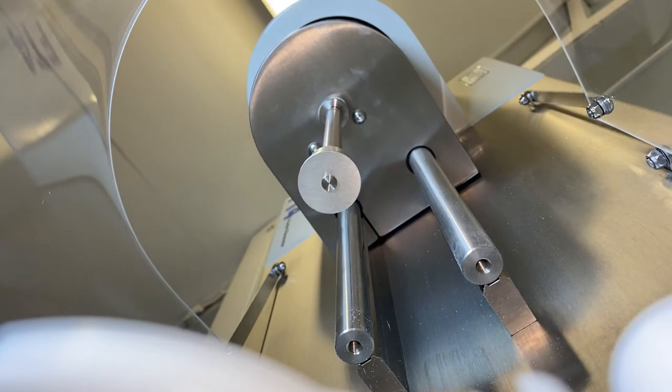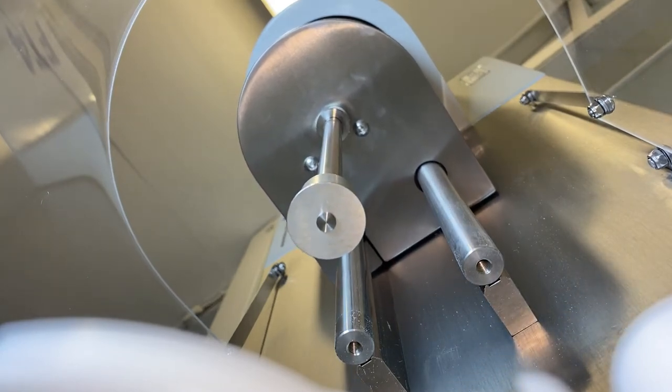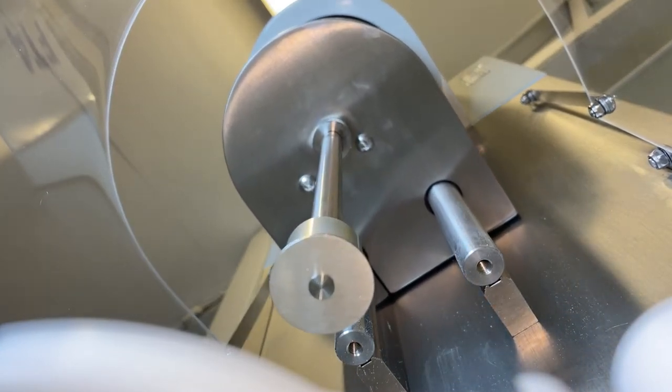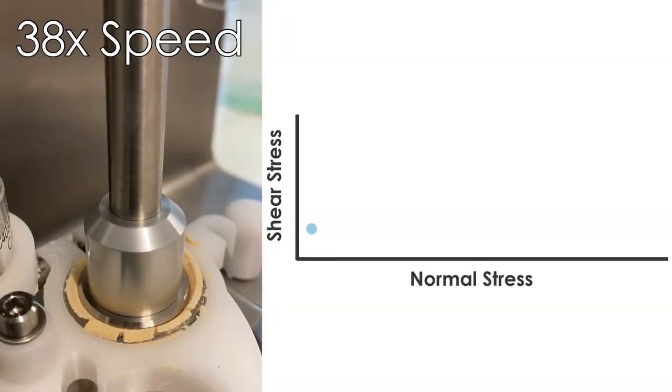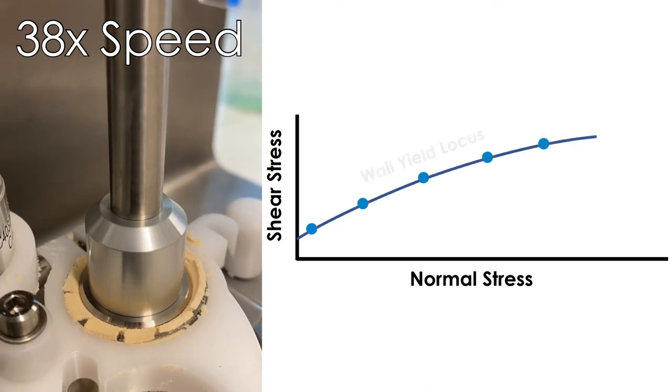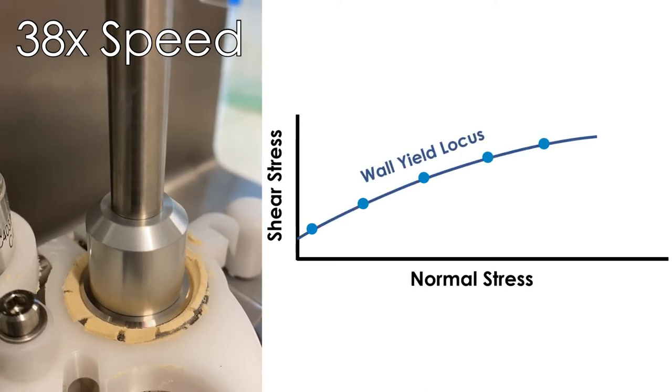Making the incorporation of wall friction measurements into plant design calculations a necessity. Measuring powder wall friction entails measuring the steady state shear stress at a range of load stresses as a powder slides against a surface.